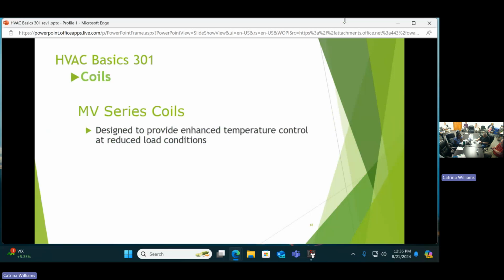So that provides enhanced temperature control under reduced load conditions. As the temperatures get warmer and warmer, take another example we're going to show you here, VAV, where they vary the airflow, not just the temperature, but the actual volume through the coil. With that reduced load, they don't need as much heat. So this is able to handle that variation by, at a certain point, shutting off the leading row of fins completely, and then your dampers will open and close to maintain the temperature based on one row only. So big benefit there. It minimizes the override, which is a big thing for some of the important labs or hospitals.